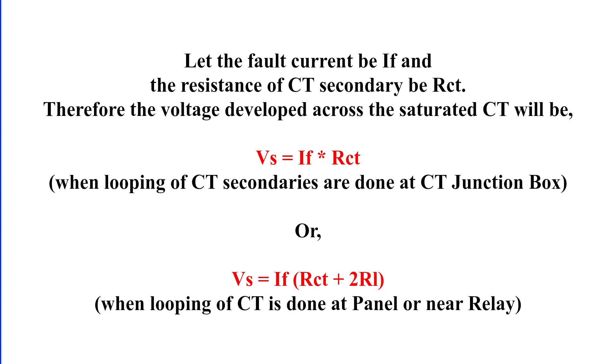This difference arises because paralleling can be done either at the CT junction box or at the panel. If paralleling is done at the CT junction box, then only the CT's secondary resistance matters. However, if paralleling is done at the relay panel, we must also account for the lead resistance from the CT to the panel.